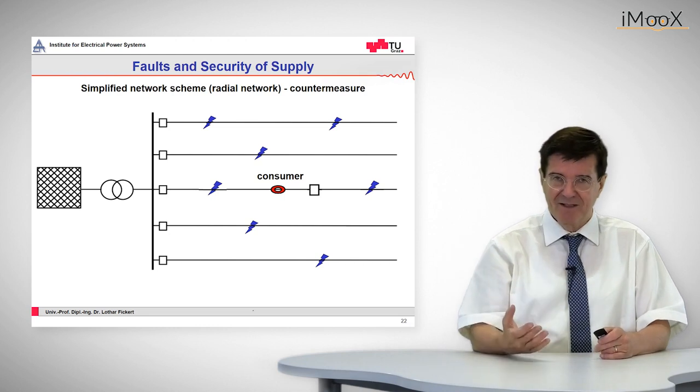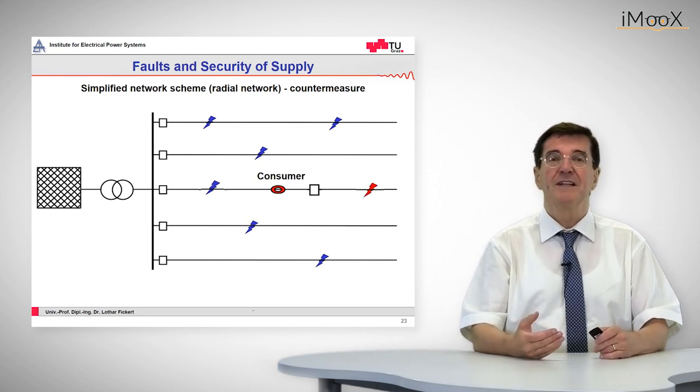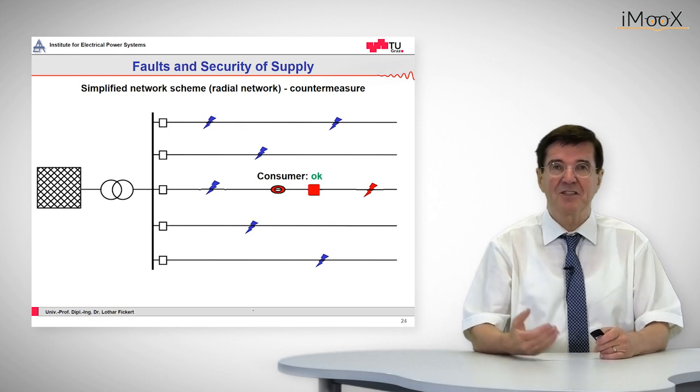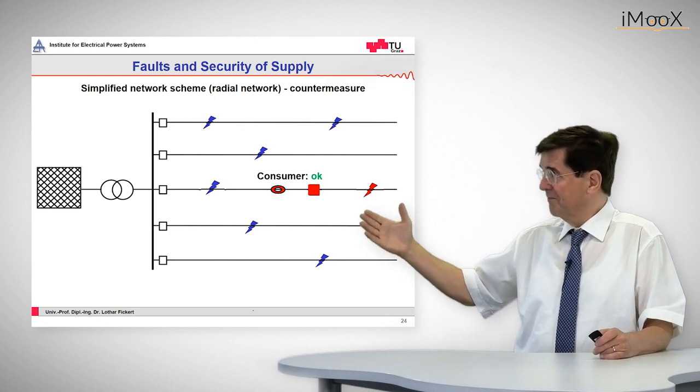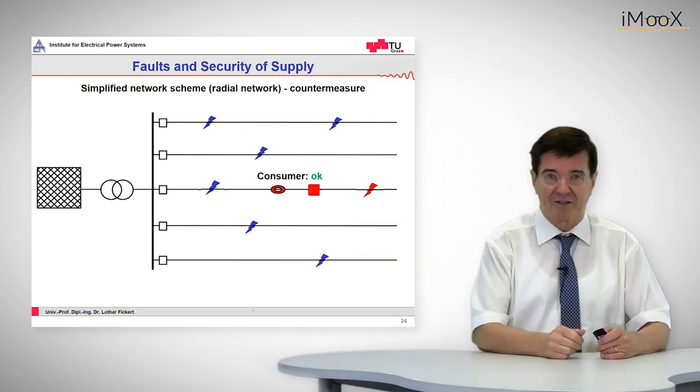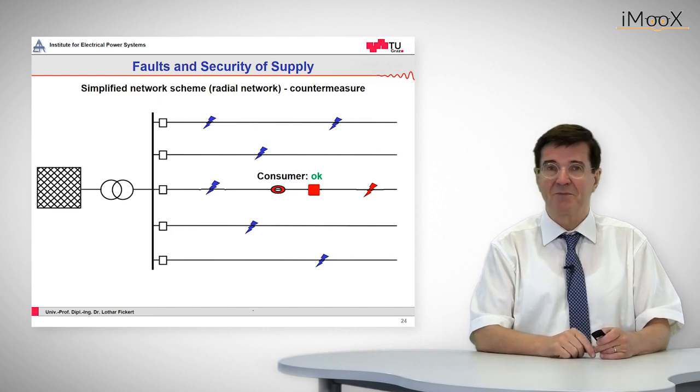Now let's play the same procedure again. The fault occurs, is detected by the protection downstream and tripped out. That means the supply from the source to the consumer is not interrupted. The consumer has experienced a little voltage dip but not more.